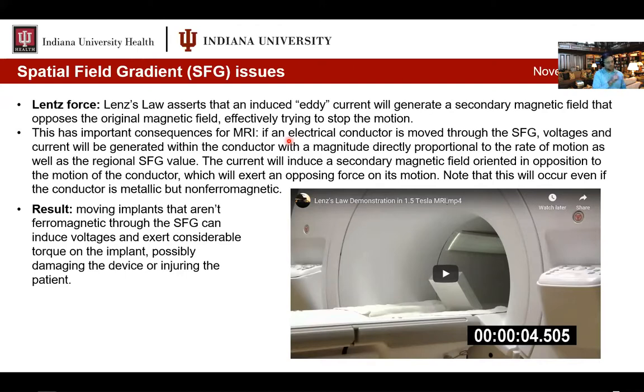When those electrons flow in circles, they create a perpendicular magnetic field that's opposite the main field, and it makes it hard all of a sudden to push. So anyone that's taken aluminum plates into the MR scanner knows if you try to twist them around, all of a sudden it's like it's stuck in place. This is because of Lenz's forces and the eddy currents that they create. This does have important consequences in MRI. If an electrical conductor is moved through the spatial field gradient, you will have voltages and current generated in that conductor with a magnitude that's directly proportional to the rate of motion. So that gets us back to moving slowly in the magnetic field, as well as the regional spatial field gradient.